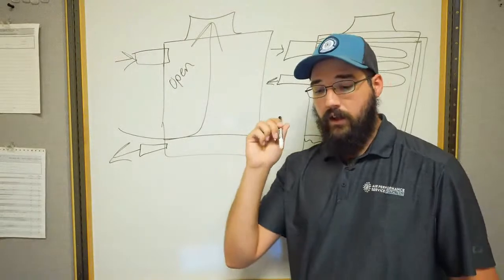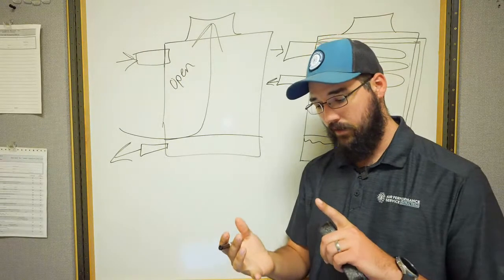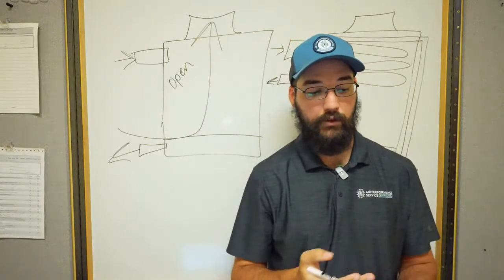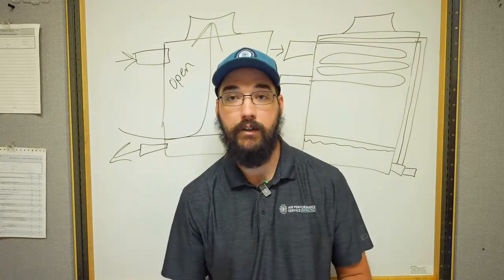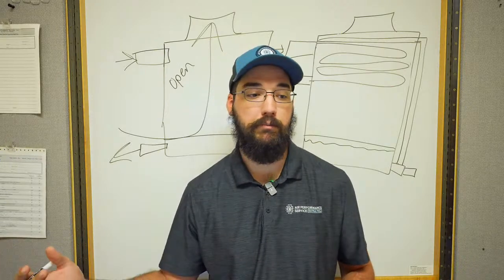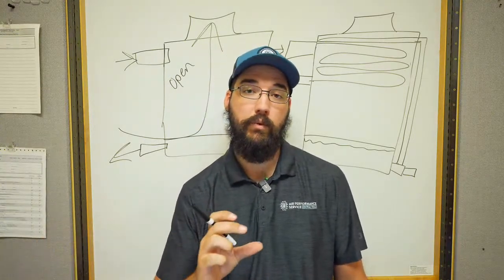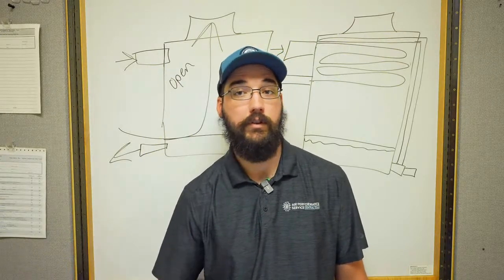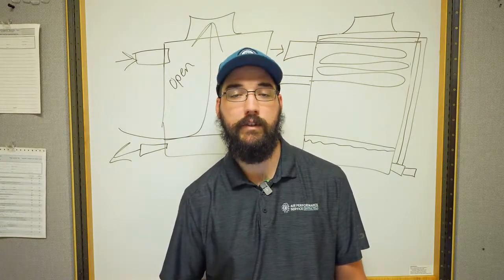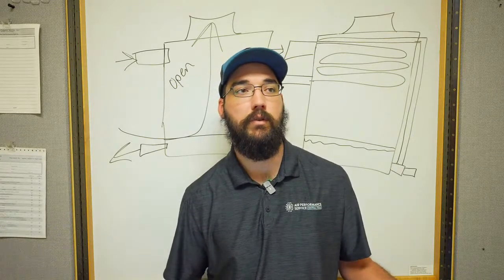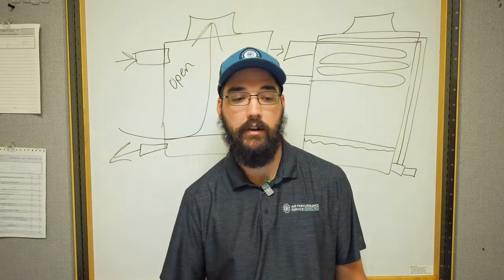In terms of startup, towers are fairly simple. If we don't have a control panel, we'll have a basin heater that has just a line thermostat — typically a 120 or 240 circuit going to a thermostat which ties into the basin heater. It receives power when the thermostat closes and energizes the heater based off basin temperature. I usually set those somewhere between 45 and 55 degrees. You can set them lower, but you want to be careful not to set them too low.